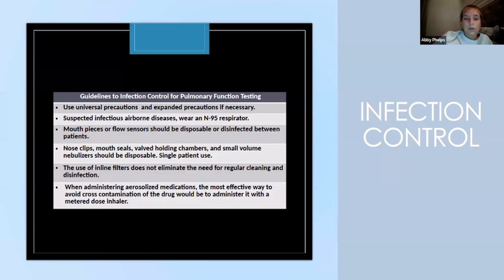Nose clips, mouth seals, valve holding chambers, and a small volume nebulizer should be disposable, and those should be single patient use. The use of inline filters does not eliminate the need for regular cleaning and disinfection. When administering aerosolized medications, the most effective way to avoid cross-contamination of the drug would be to administer it with a metered dose inhaler.